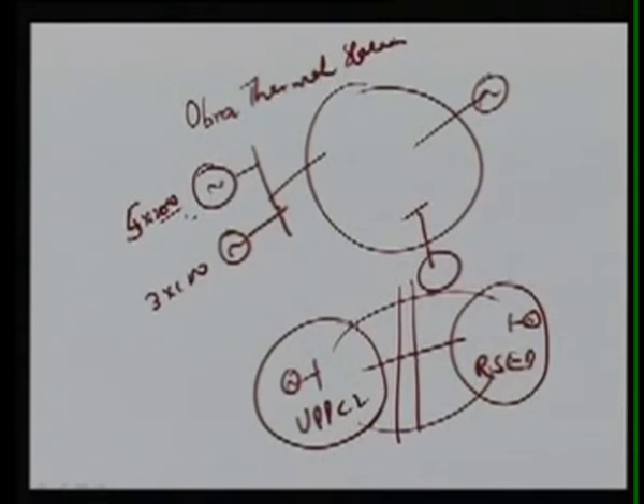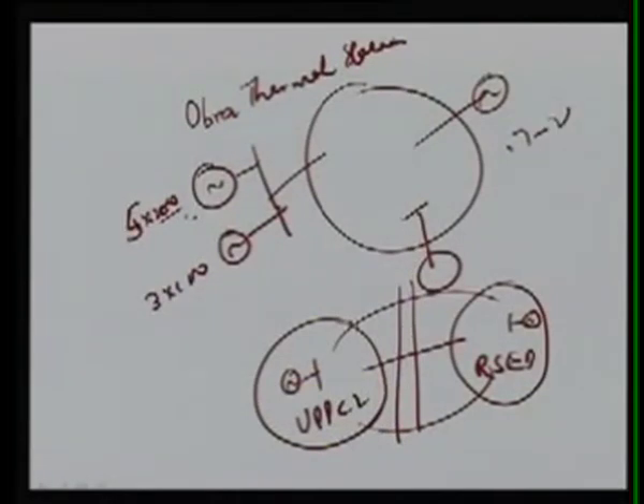So the difference between your local mode - where one unit of any power plant is oscillating with the rest of the system, at 0.7 to 2 hertz - and the inter-area modes of oscillation, where one area may be a few generators or a complete state, and these generators in that area are oscillating with the generators in another area - that is why it is called inter-area.